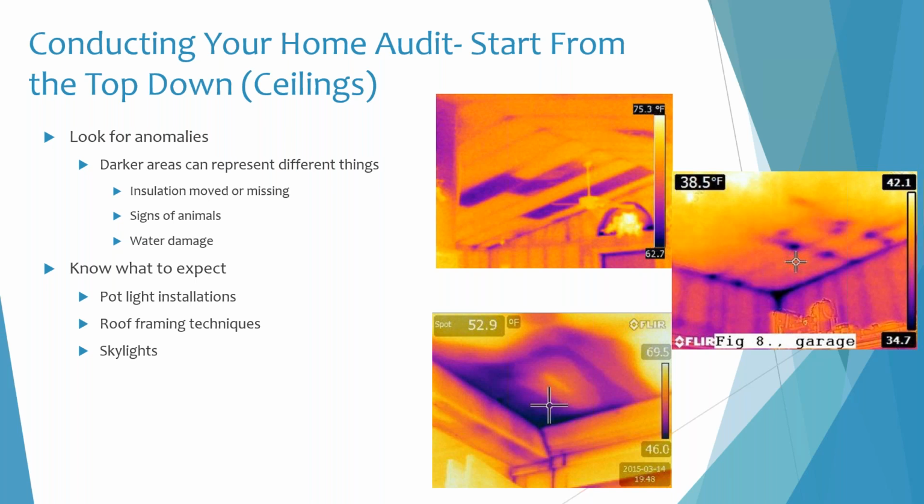What you'll find is that with a lot of retrofits of these pot lights, you'll have this big cavity with a lack of insulation and then a lamp which no longer heats that cavity. And so these will show up as issues in your thermal image scan. But it's something that you should not be making recommendations around, because what you're ultimately encouraging is for the owner to violate code by placing insulation around their space.